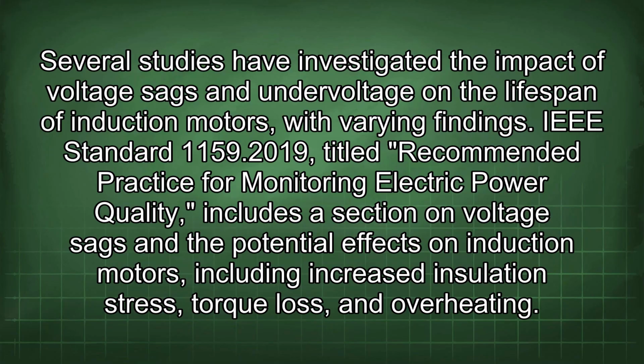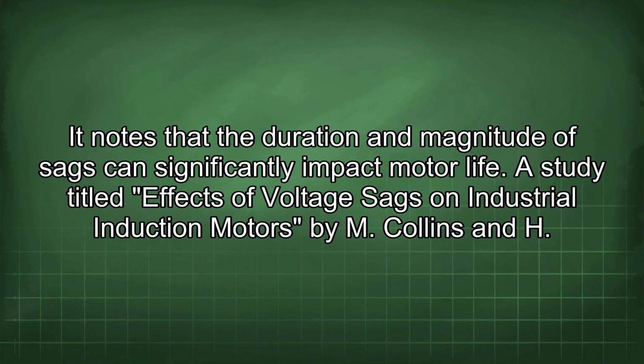Several studies have investigated the impact of voltage sags and undervoltage on the lifespan of induction motors, with varying findings. IEEE Standard 1159.2019, titled Recommended Practice for Monitoring Electric Power Quality, includes a section on voltage sags and the potential effects on induction motors, including increased insulation stress, torque loss, and overheating. It notes that the duration and magnitude of sags can significantly impact motor life.